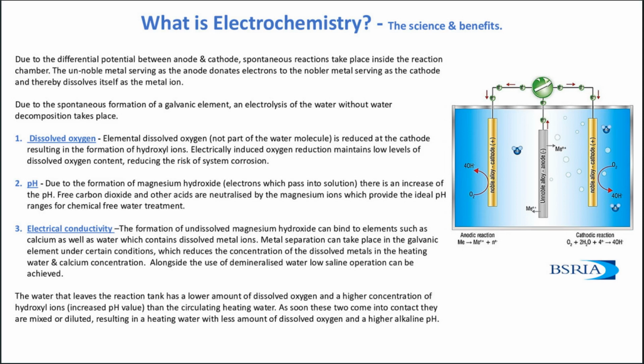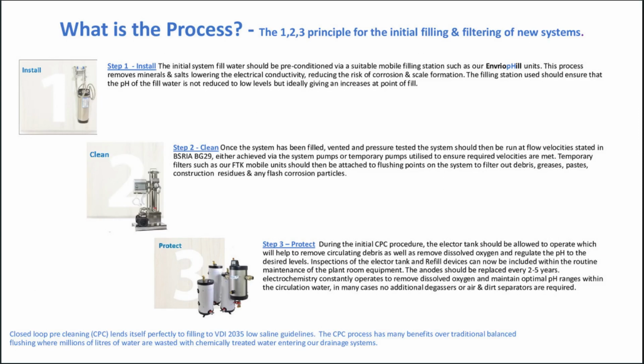The water that leaves the reaction tank has a lower amount of dissolved oxygen and a higher concentration of hydroxyl ions, so we increase the pH value, than the circulating water. As soon as these two come into contact, they are mixed or diluted, resulting in a heating water with a lesser amount of dissolved oxygen and a higher alkaline pH. So what is the process? Again, we're following the 1, 2, 3 process.